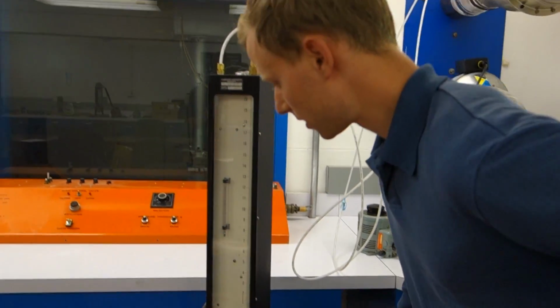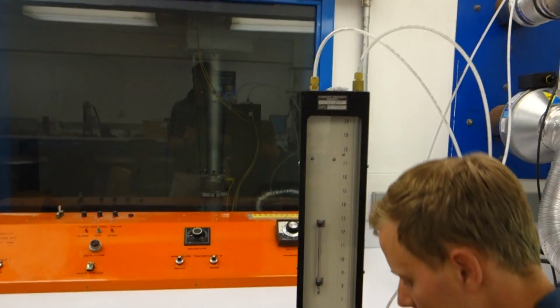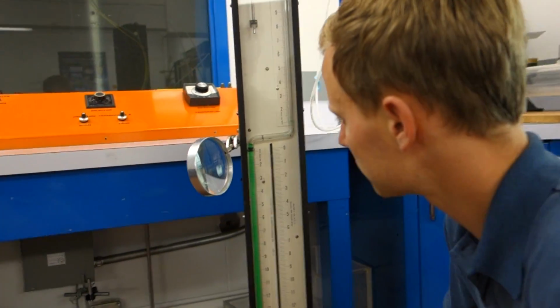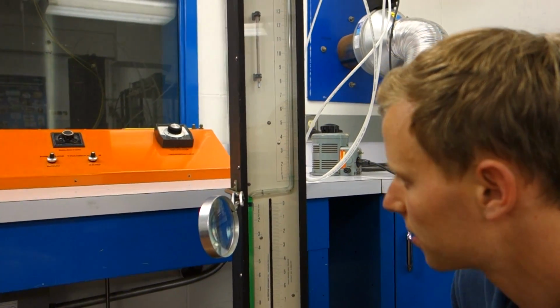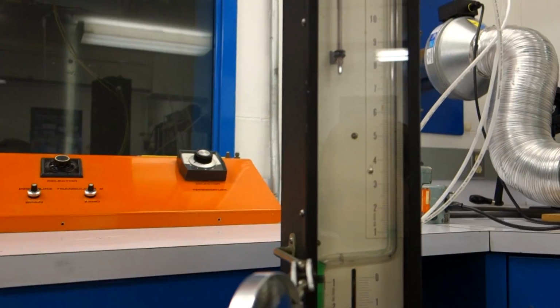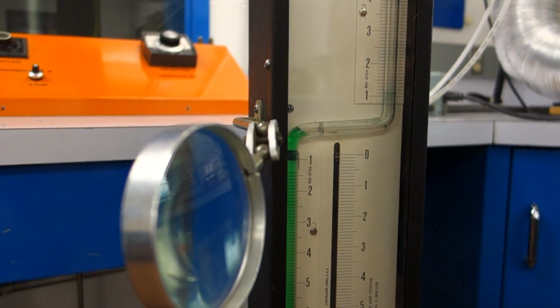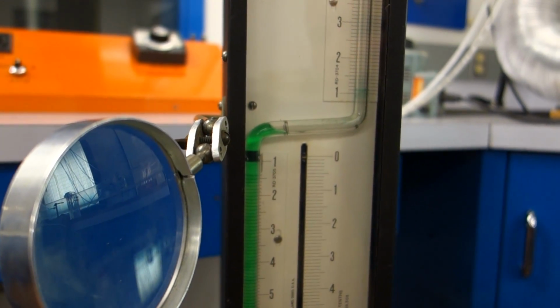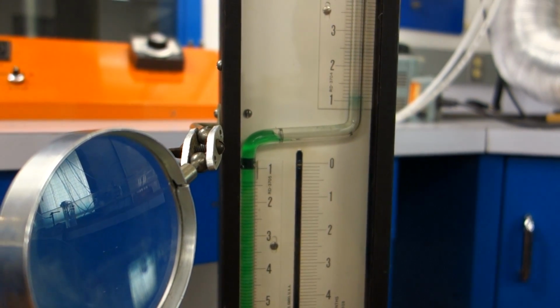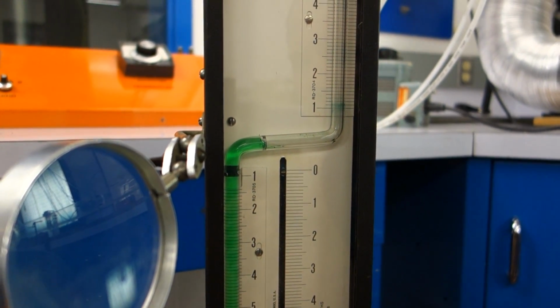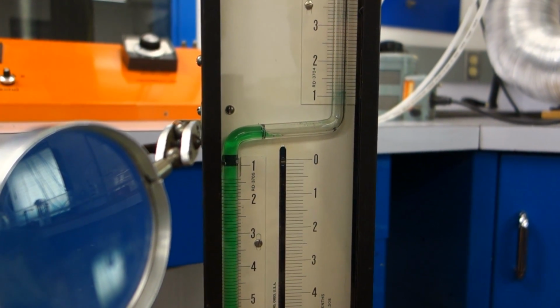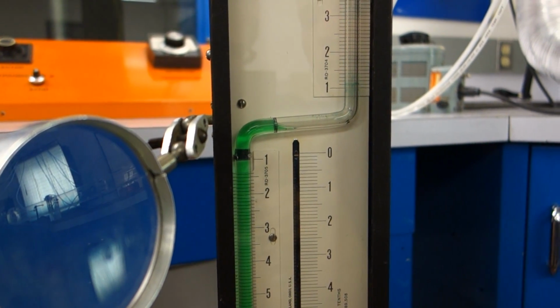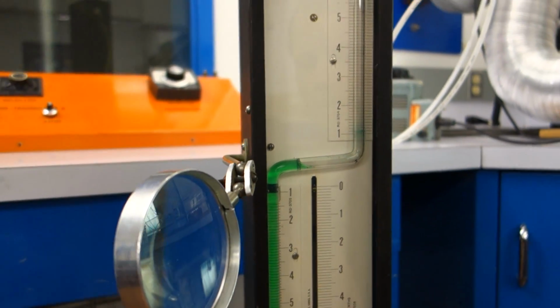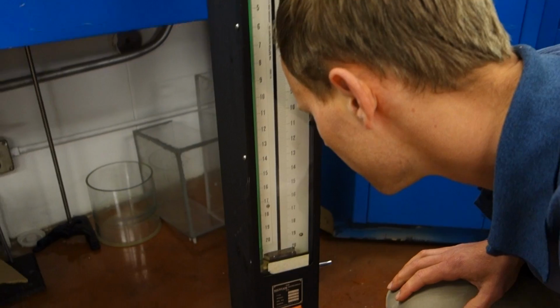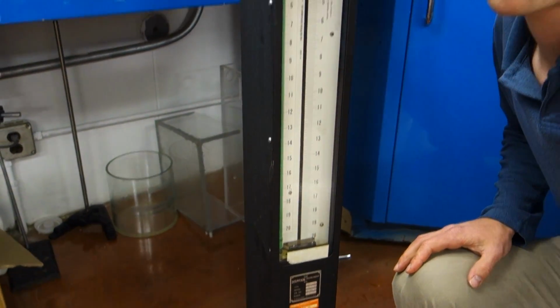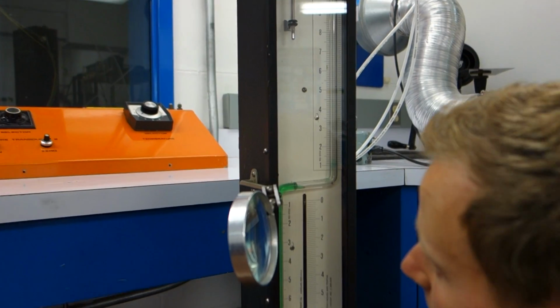As I said before, there's a reservoir on the back of this device, which we can't see right now. But by raising and lowering the reservoir with no pressure across it, I can read the other side as well. And I'll want it to be just so that the meniscus is in between the black lines. That's pretty good. So I'm reading 0.0 and 54/1000, so 0.054 is our zero. I would write that number down so I don't forget it.